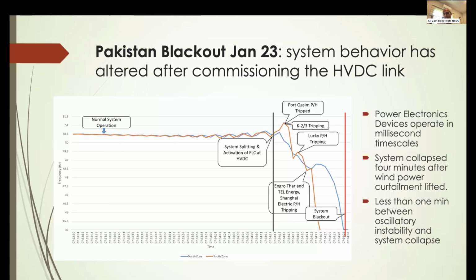Here's an example of what happened to us. The two lines, orange and blue, are the system frequency for the north and south zones. We have longitudinal networks reflecting our geography, about 1,500 kilometers from one end to the other, giving us a northern and southern zone. Most of our newer, cheaper generation is in the south, but 80% of our load is in the north.